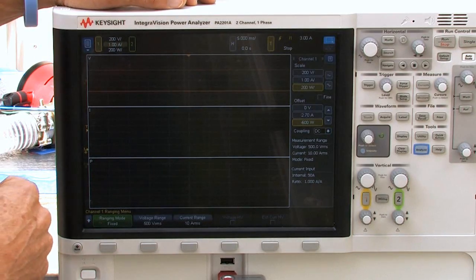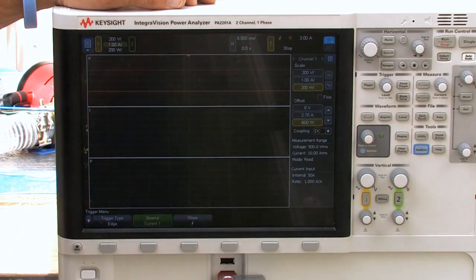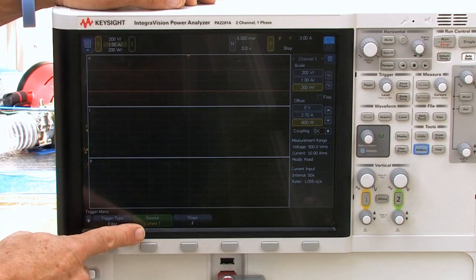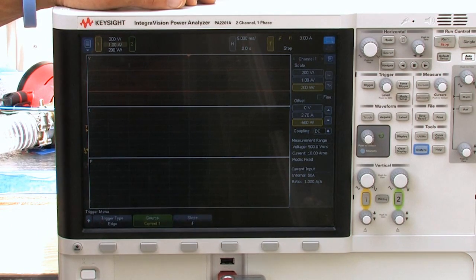Next thing I want to do is look at triggering because we're going to be triggering on that current spike. So push trigger and make sure that we have current as a source, so yes, current channel one is that source. We'll play around with the trigger level and see that it's significantly above zero, and there we are at three amps, so we should be triggering on three amps. So I think we're set up well.